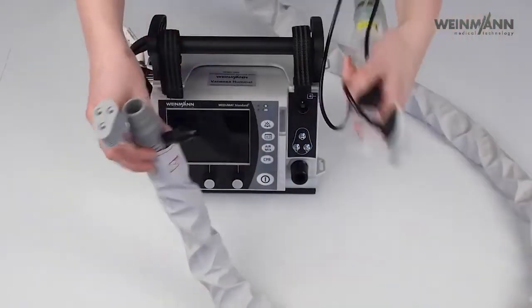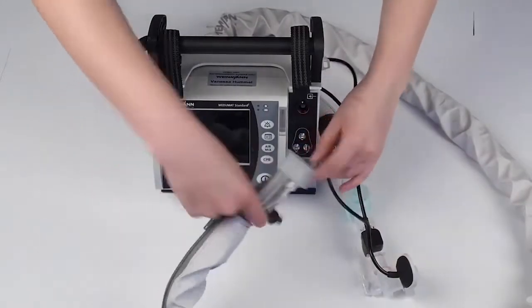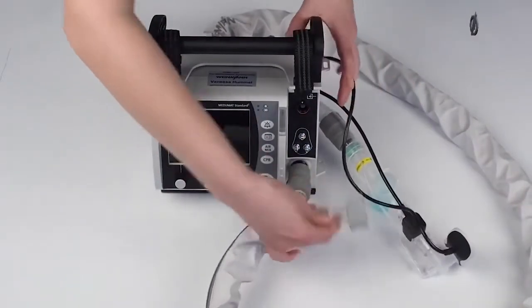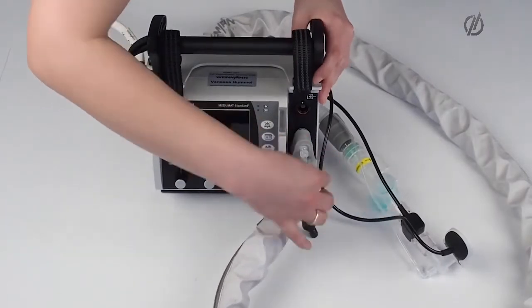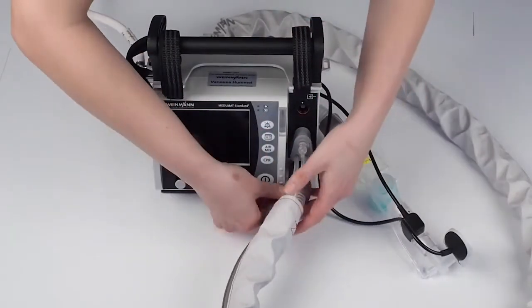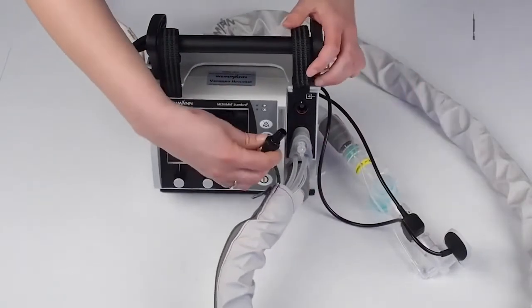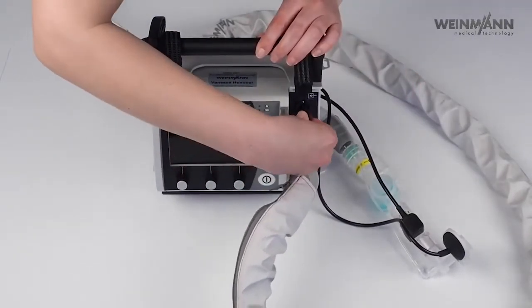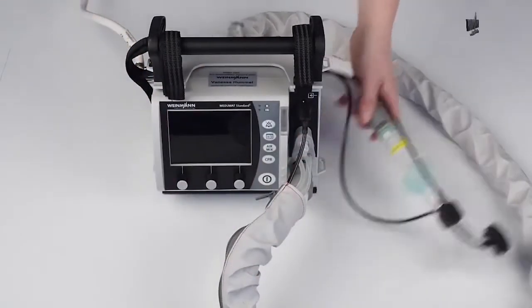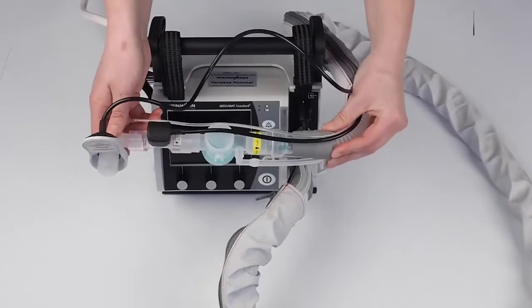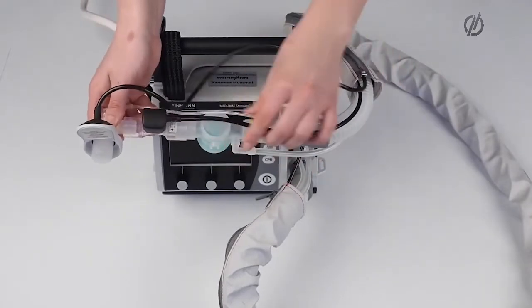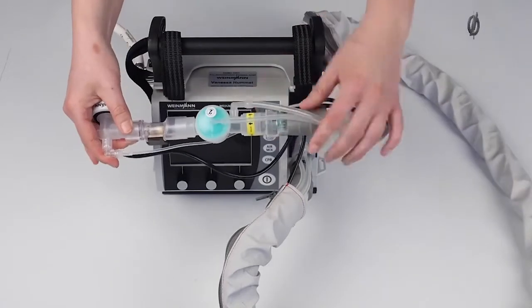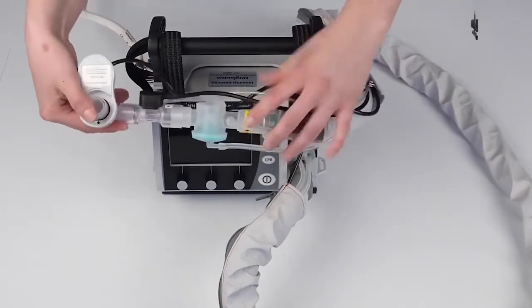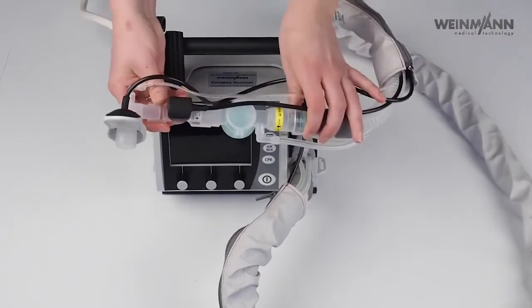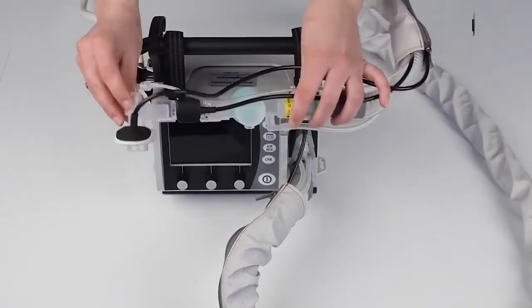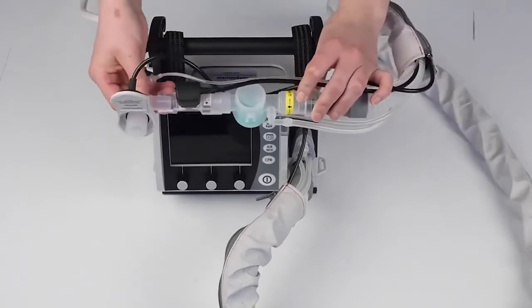So we have a single limb patient circuit here. Just connect the patient hose here, our measurement hose system with the end-tidal CO2 measurement, which is optional, the pressure measurement and the PEEP regulation, and also our connector for the proximal flow sensor. On the other side, this is the patient side of the circuit, we have the patient valve with the PEEP regulation here, with the pressure measurement, with the proximal flow measurement, which is also optional, and the side stream CO2 measurement, which is also optional.